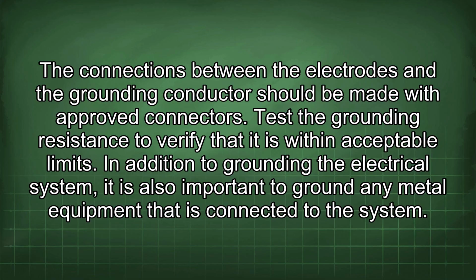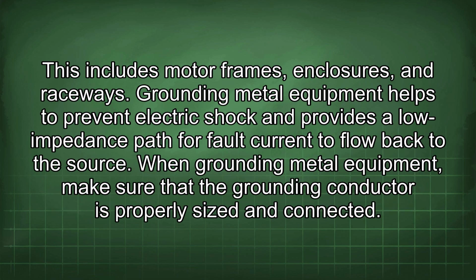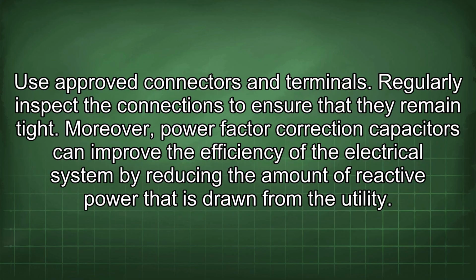In addition to grounding the electrical system, it is also important to ground any metal equipment that is connected to the system. This includes motor frames, enclosures, and raceways. Grounding metal equipment helps to prevent electric shock and provides a low impedance path for fault current to flow back to the source. When grounding metal equipment, make sure that the grounding conductor is properly sized and connected. Use approved connectors and terminals. Regularly inspect the connections to ensure that they remain tight.